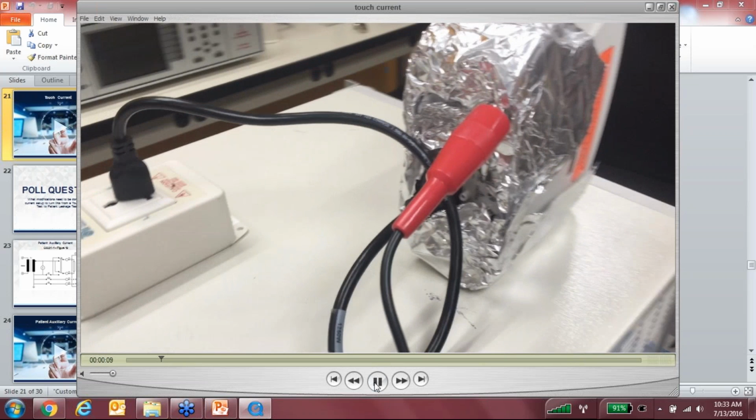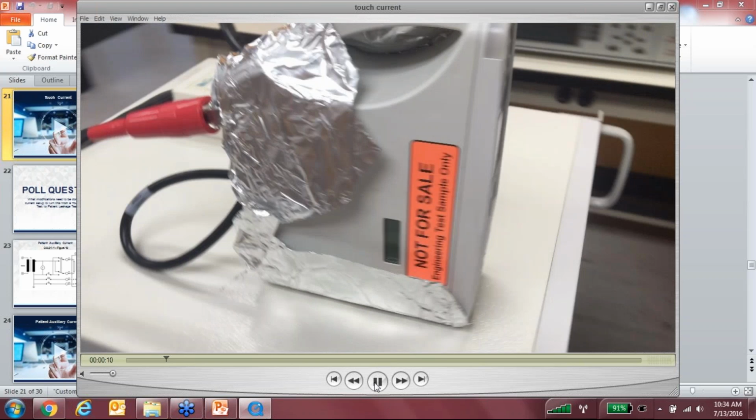All right, so those connections are pretty self-explanatory, right? Again, I have one side of my measuring device on a touch point of my DUT and the other side referenced to the input power of my T1. So let's go to the front panel of my Omnia 2 here.